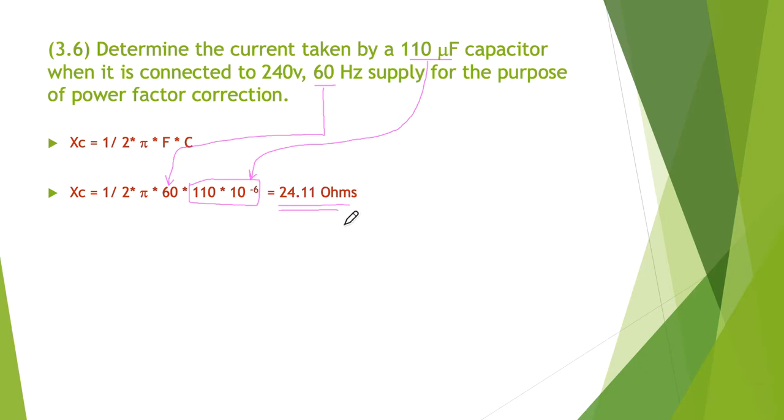Now we're down to simple ohms law, we have the voltage. The current through the capacitor is the voltage across the capacitor divided by the xc or the capacitive reactance, so we end up with 240 volts divided by 24.11 equals 9.95 amps. That's the amount of current. Two steps: we had to find out the xc for the capacitor and then determine the current through the capacitor for a 240 volt 60 hertz supply.